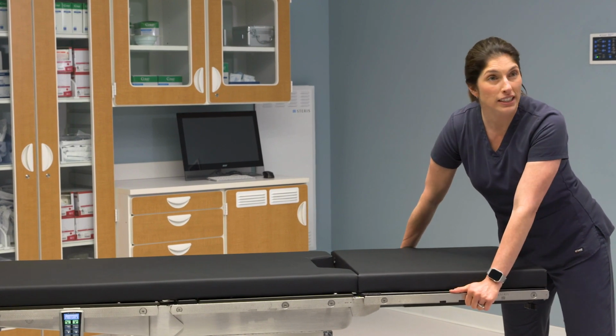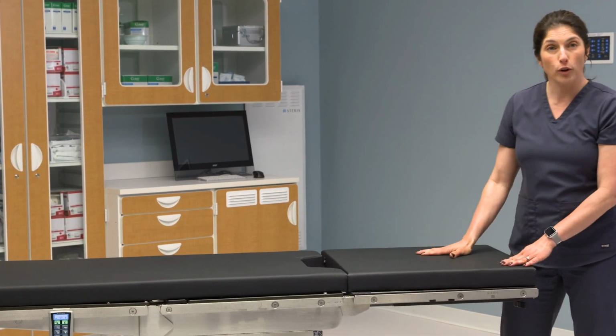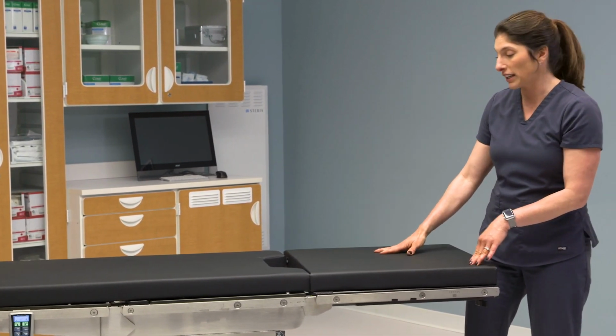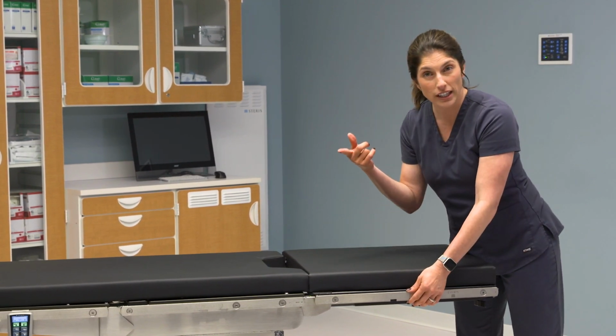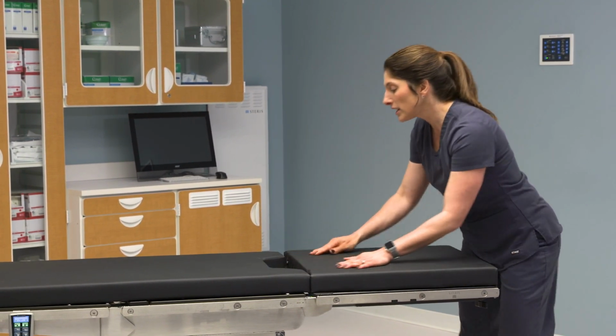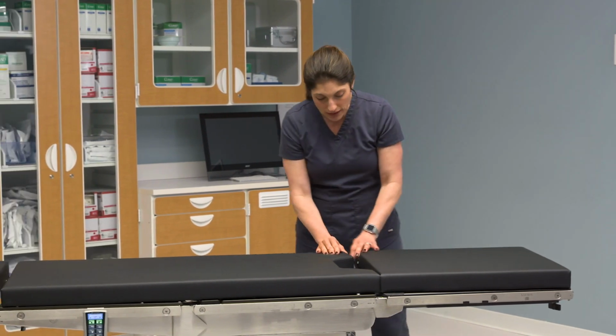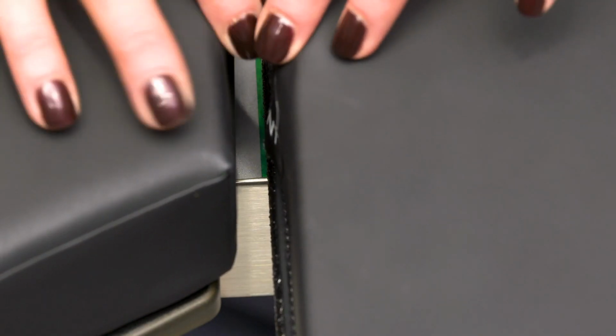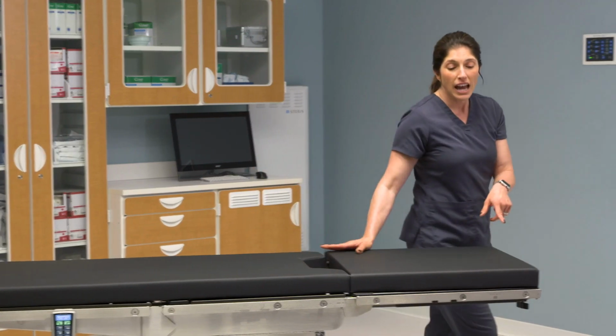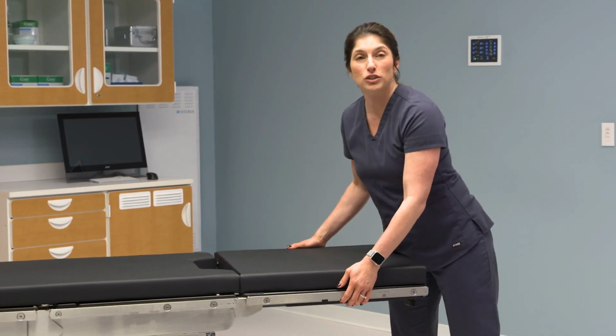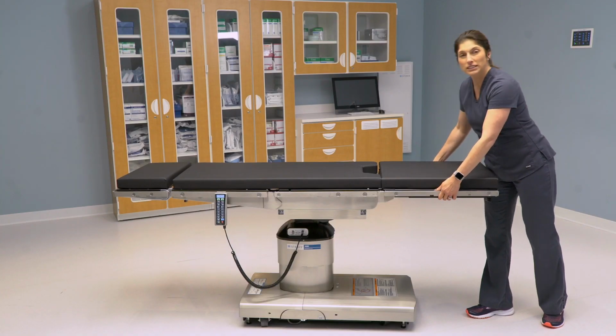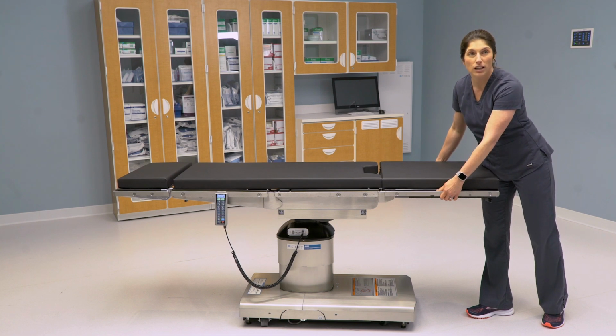There are 3 ways that I always tell people that you should confirm that you have inserted the leg section appropriately. First of all, you heard the loud click, the audio part of it. Secondly, there's a visual. You can see there's a green line here. You want to make sure that you don't see the yellow line, you only see the green line. And the third, I always tell everyone, is just a quick safety check. Once you've plugged it in, give it a quick tug back and make sure that it's locked in on both sides.